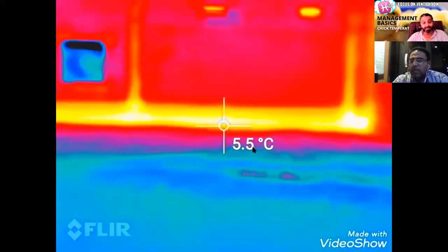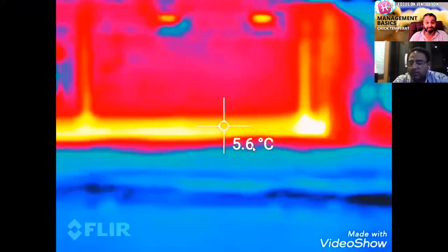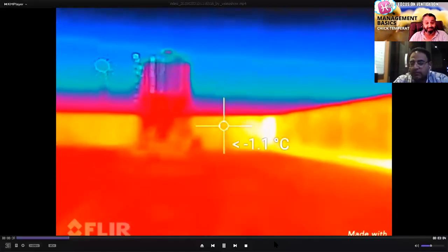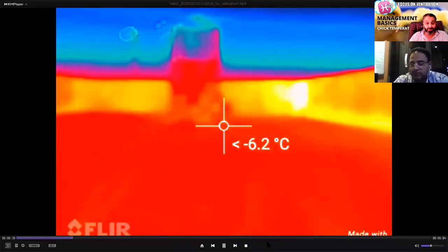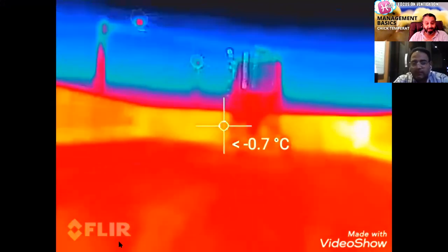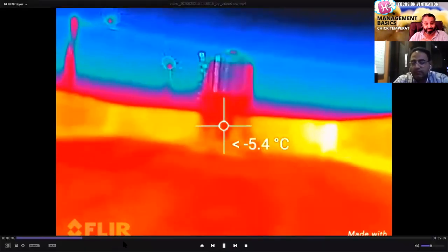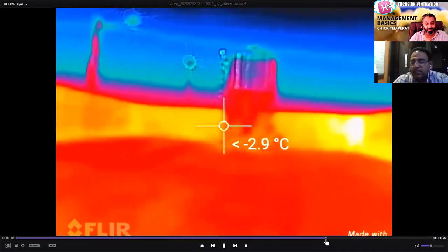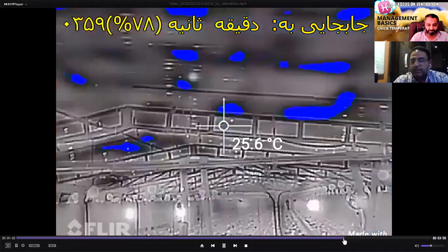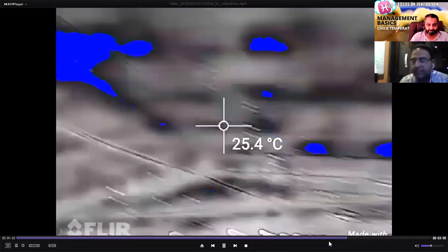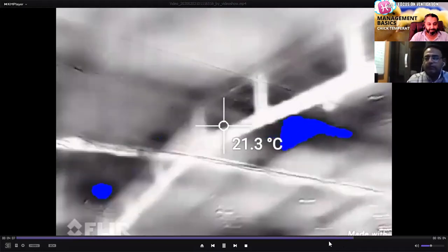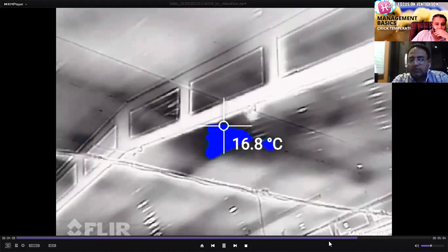Yes, a lot of cost. I am also surprised that outdoor is -6 degrees and the leakage inside is already very clear, shown by an IR camera. Yes, a thermal image from the IR camera. And inside the sheds, you can see many leakages. We had many leakages and we solved them with good sealing.